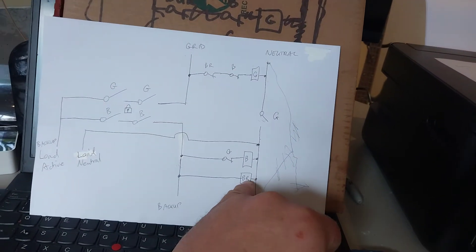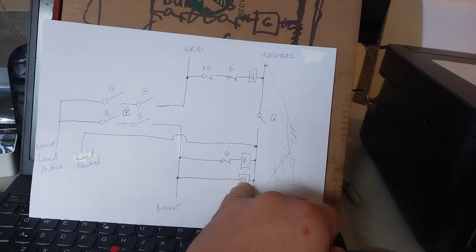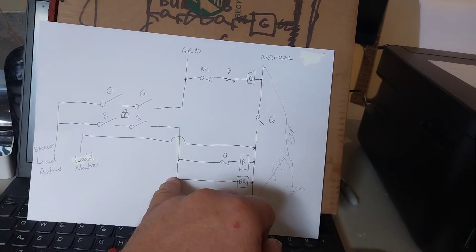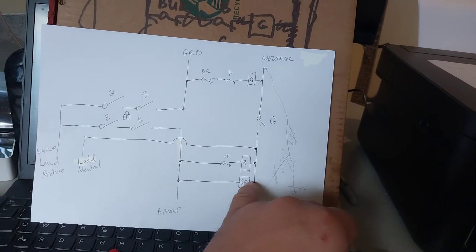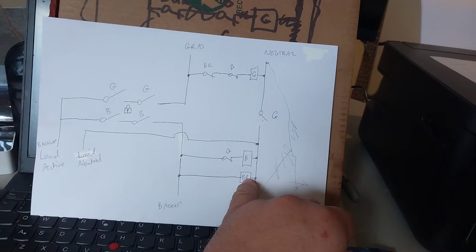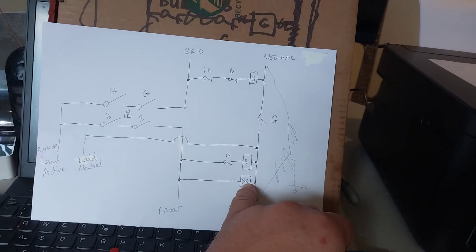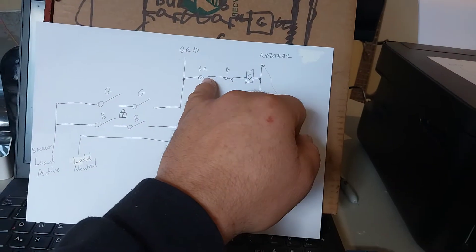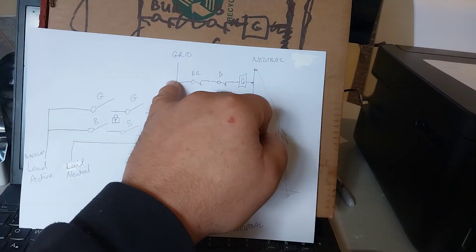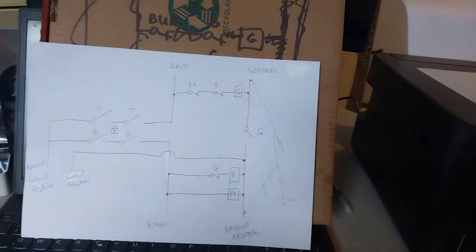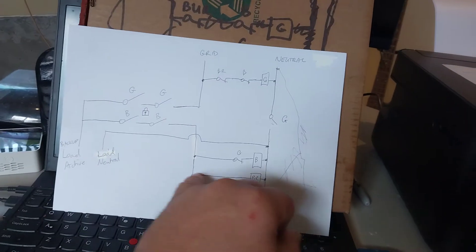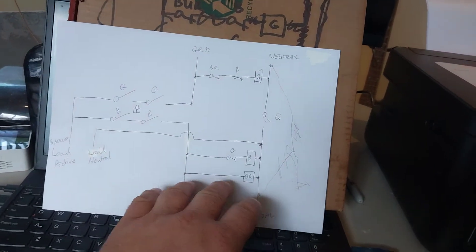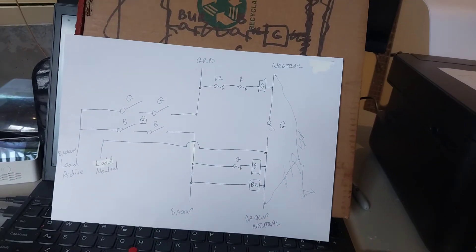That's where this relay comes in. The backup relay. So whenever there's power here there's no contacts in here stopping this coil from coming on the backup relay. You'll see a little red light in the previous video. That's it. And that means it will open the contact here providing grid power to the coil of the grid contactor. This can never go on when there's backup supply. So we have backup priority which is what we want.